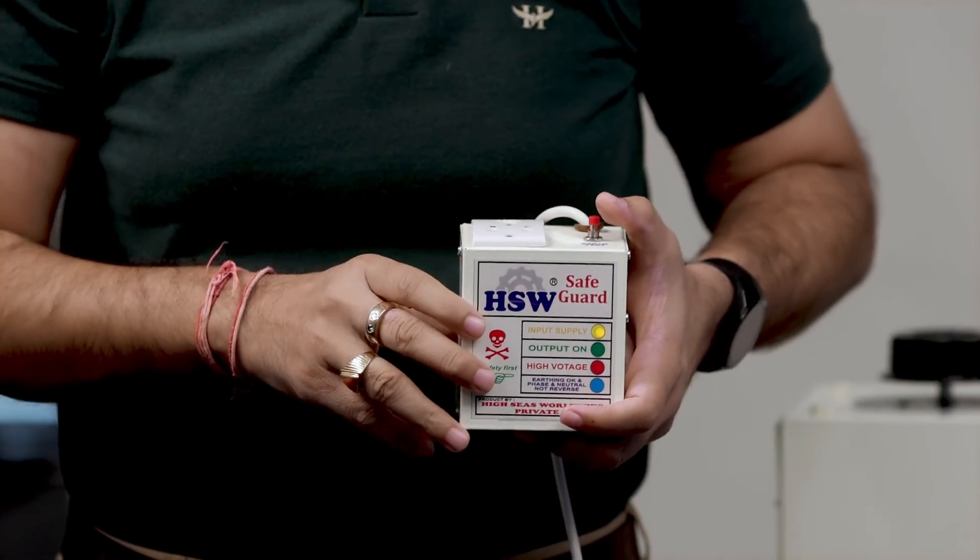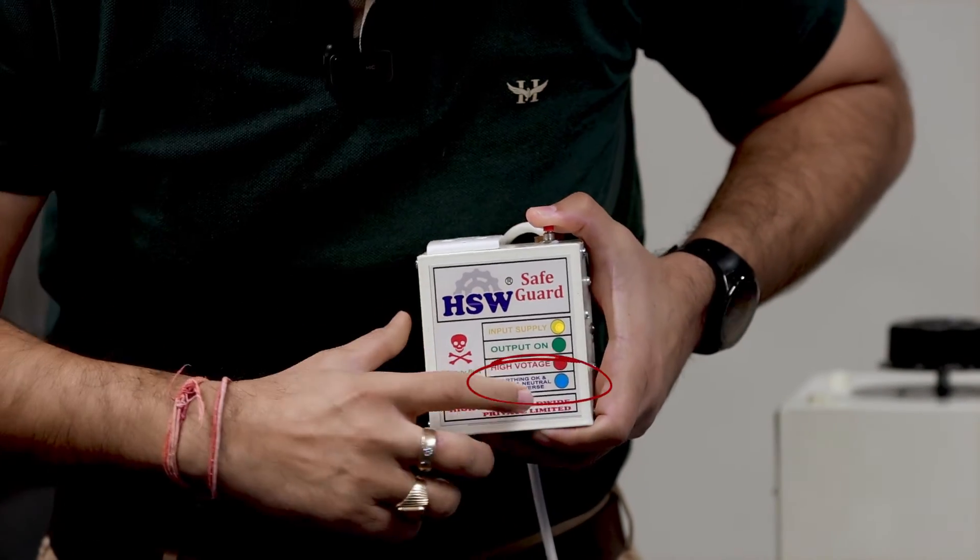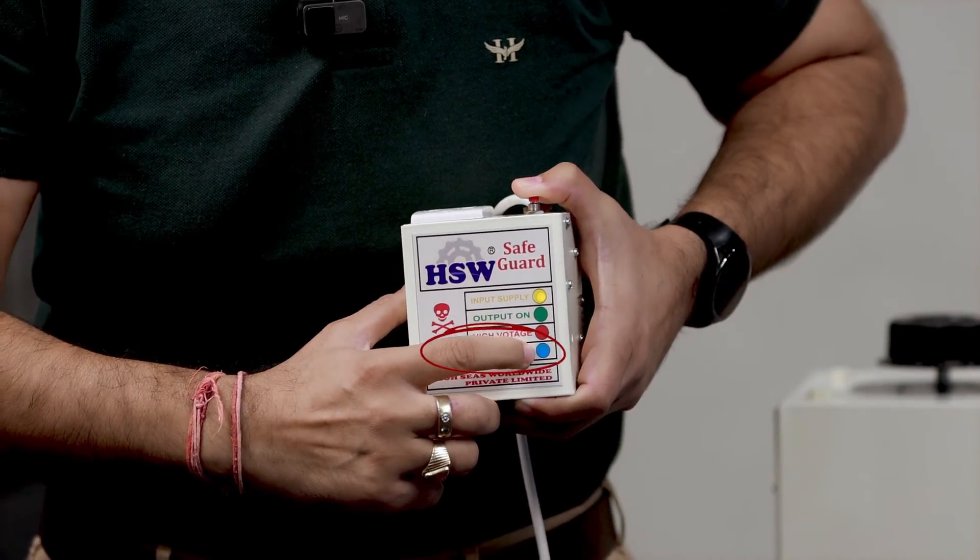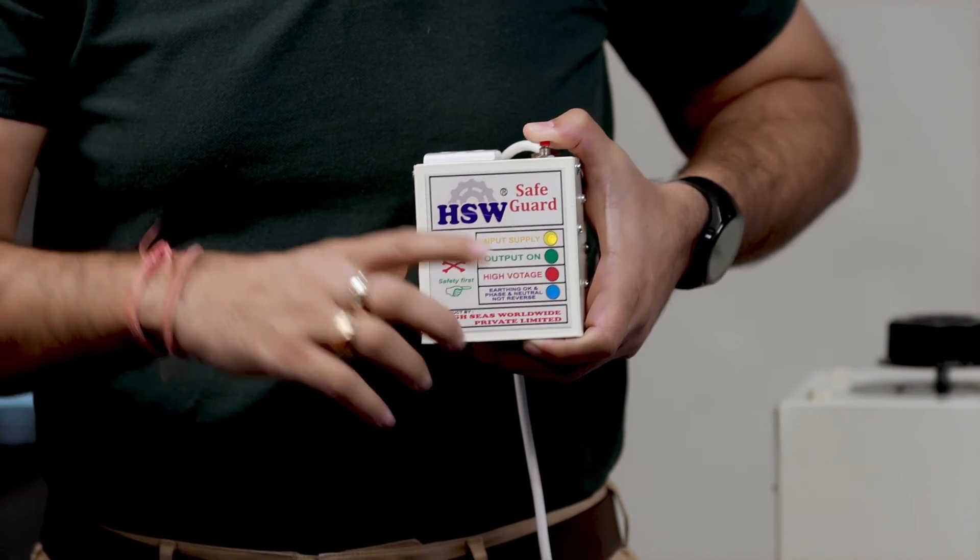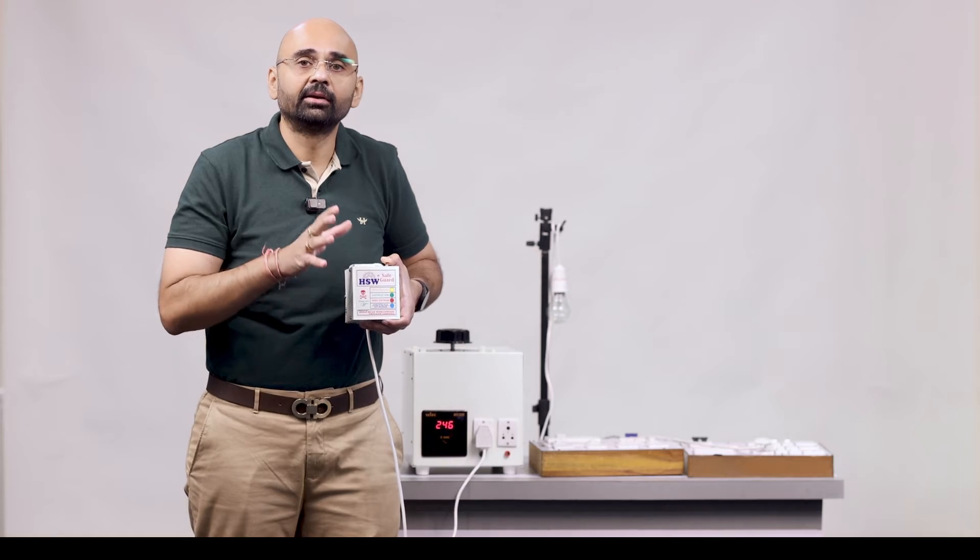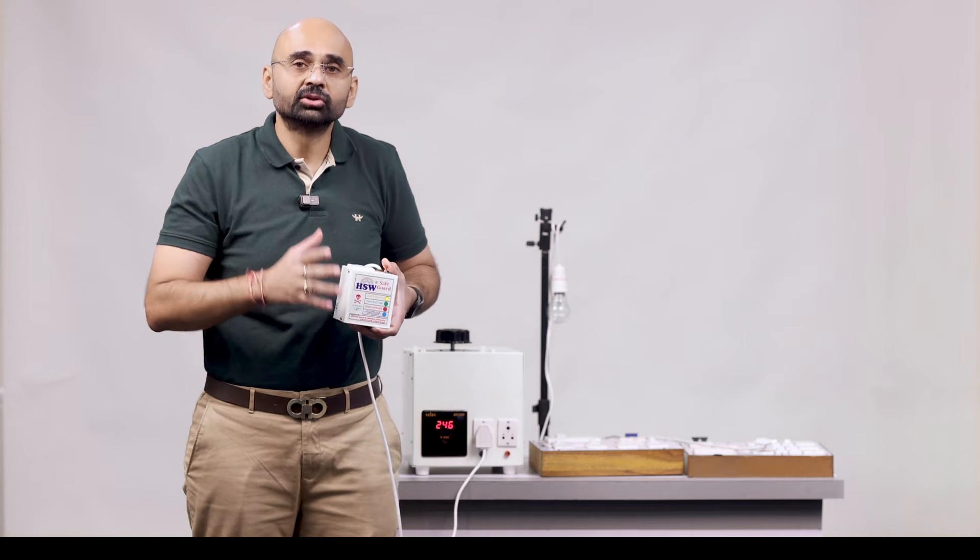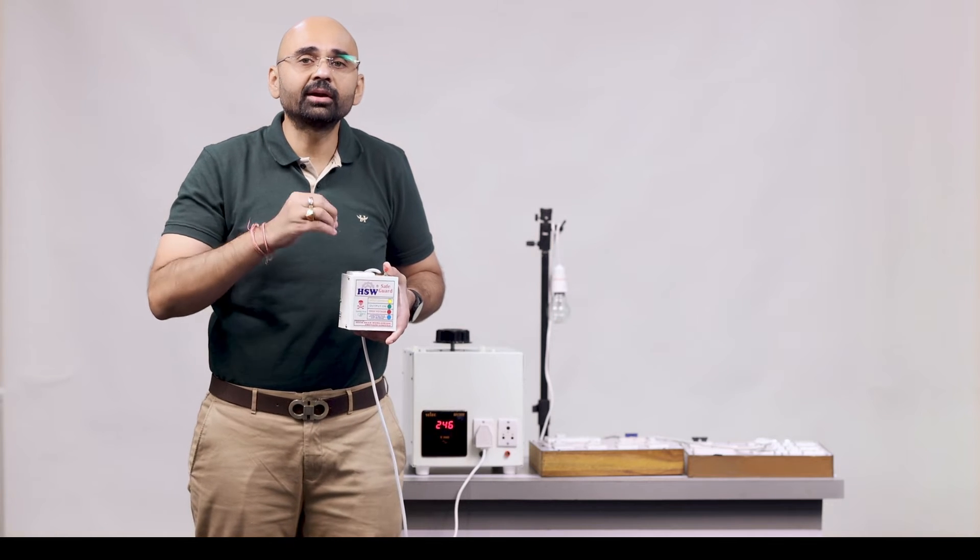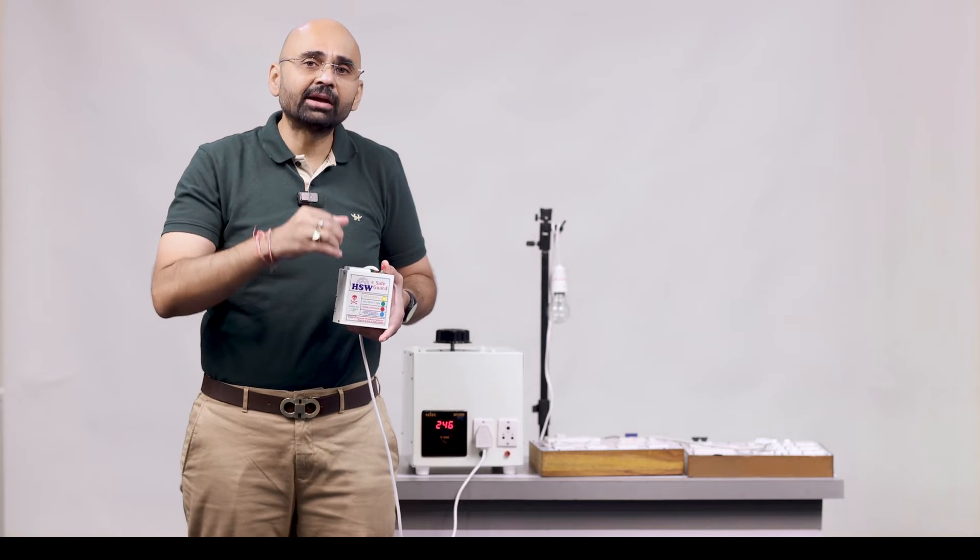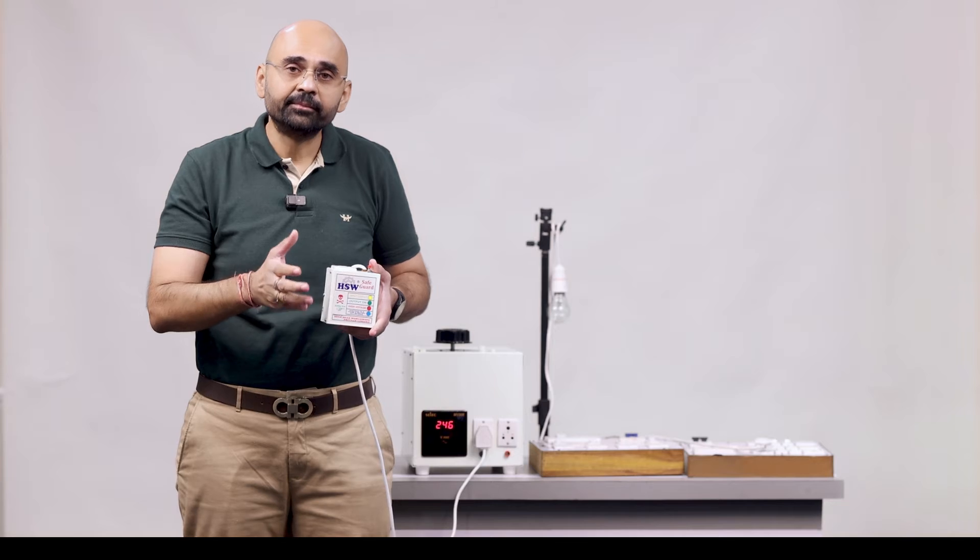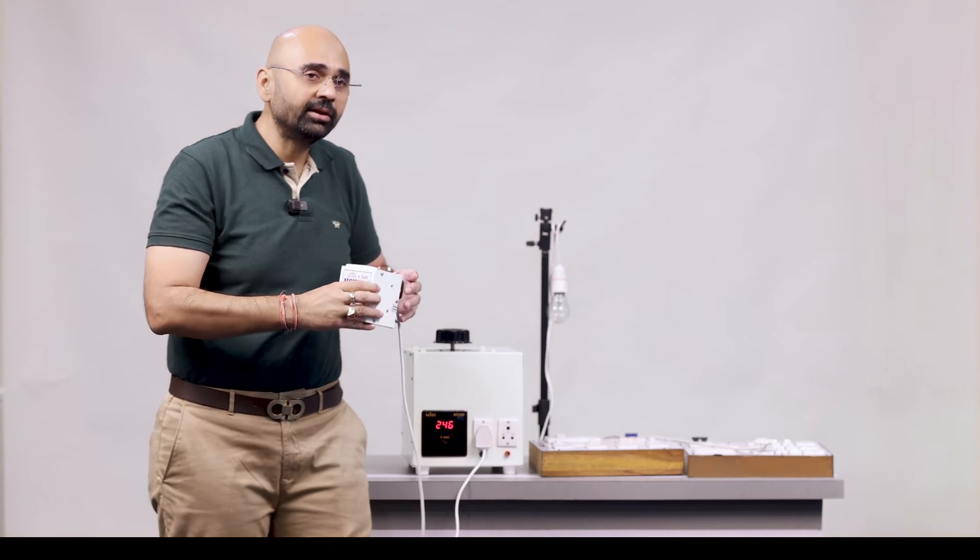So now when I press this earth test you can see that blue light is not on. That means the neutral reverse or earthing is not proper. So that's how you check the neutral reverse and earthing.